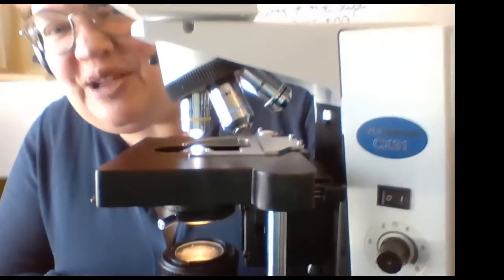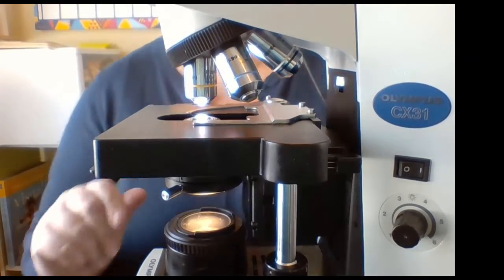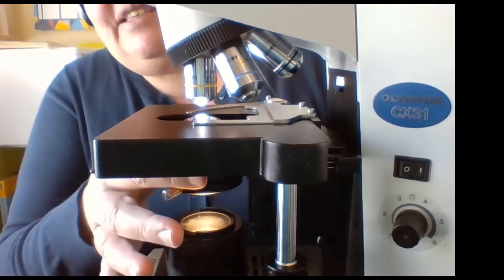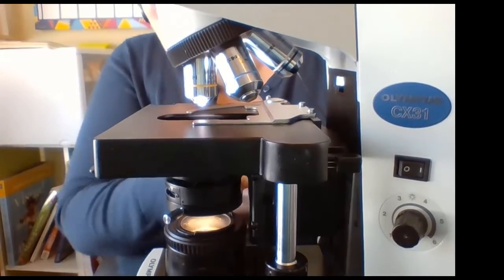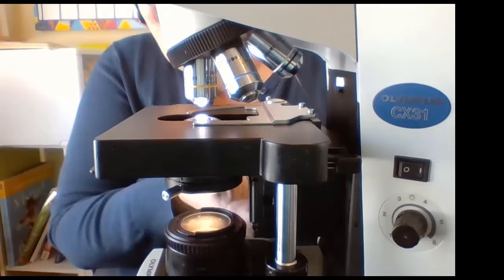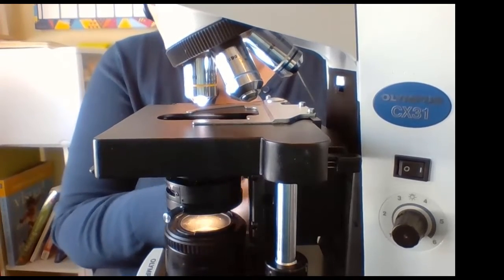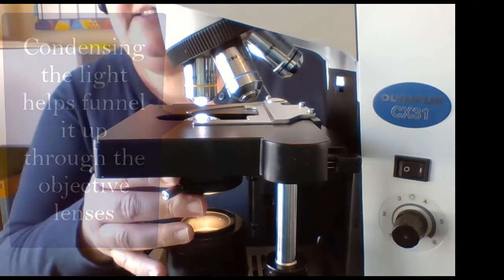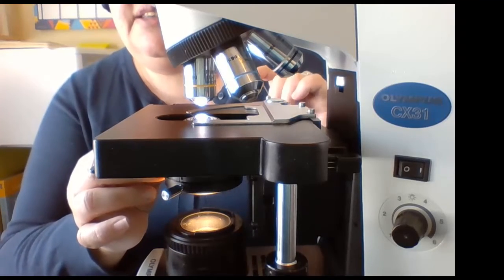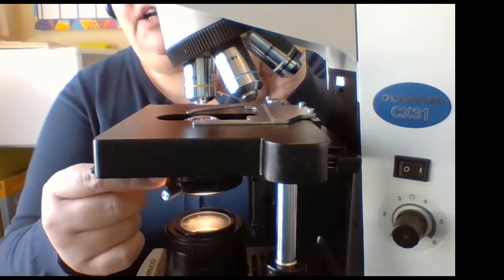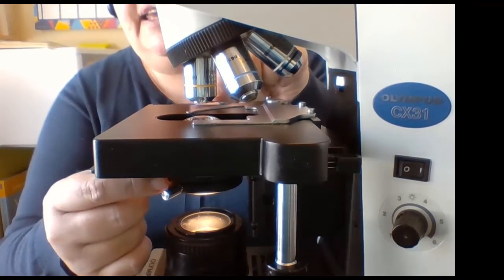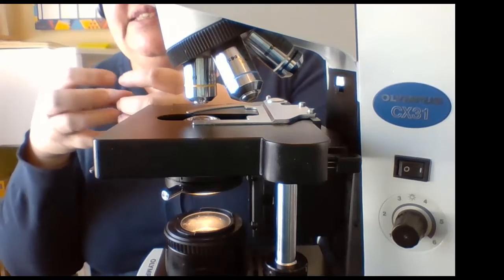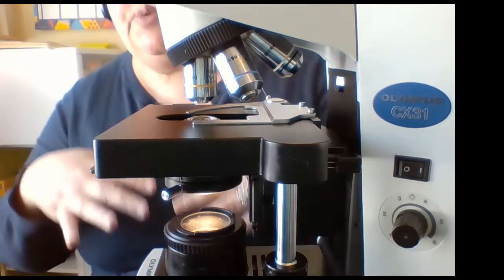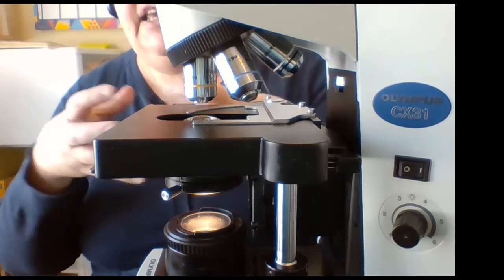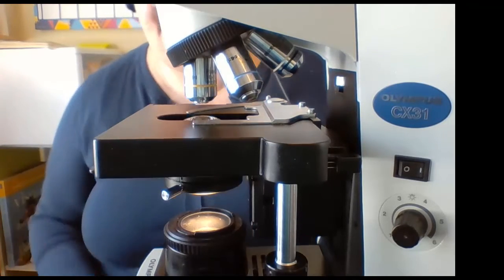This is the demo microscope, one where not all the parts are moving the way they should. Immediately under the stage is the condenser. And I'm going to use this condenser knob to move the condenser up and down. And you can see that that condenser moves up and down as I turn this knob. Okay, that's going to help condense the light. And inside of the condenser is an iris diaphragm. And so if I slide that back and forth, you can see that we are adjusting the light because it opens and closes a diaphragm inside that condenser. So raising and lowering the condenser affects the light, and opening and closing that iris diaphragm affects the light.